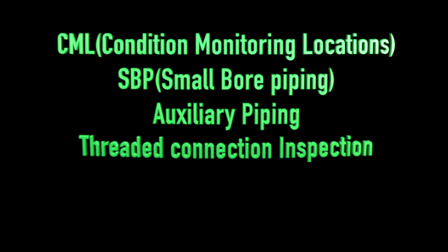Next, we can discuss CMLs, small bore piping, auxiliary piping and threaded connection inspection. The first one, external thickness measurement inspection. To satisfy inspection interval requirements, each thickness measurement inspection should obtain thickness readings on a representative sampling. It's called CMLs. The sampling also must include CMLs with the earliest renewal date as of the previous inspection. The more CMLs measured for each circuit, the more accurately the next inspection date will be projected. You should use only CML instead of TML.